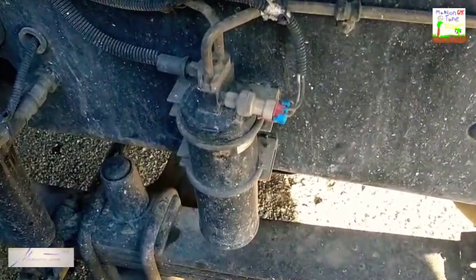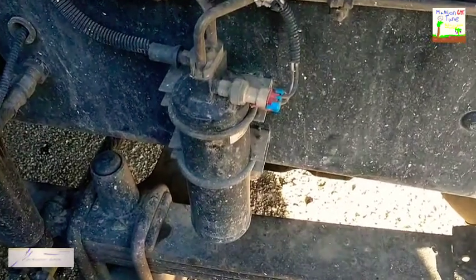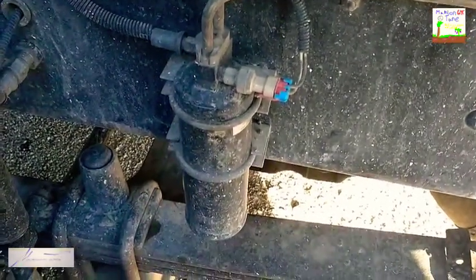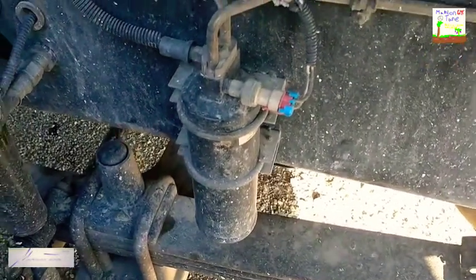The dryer is fairly new, but since the system was open — it had a hole in that condenser — we're going to go ahead and replace the dryer as well. So without further ado, let's go on with it.